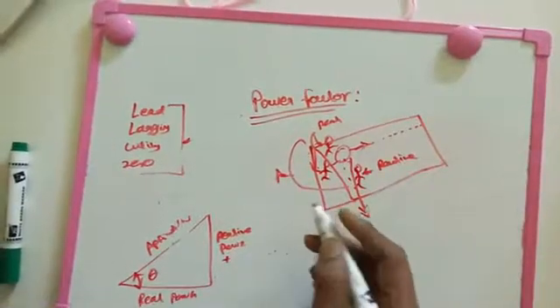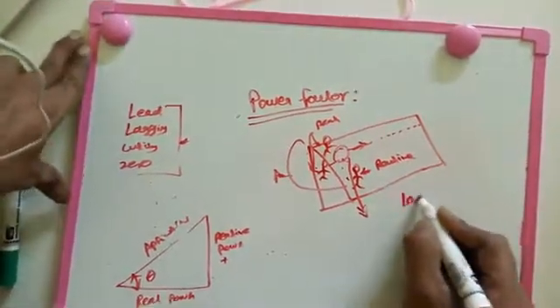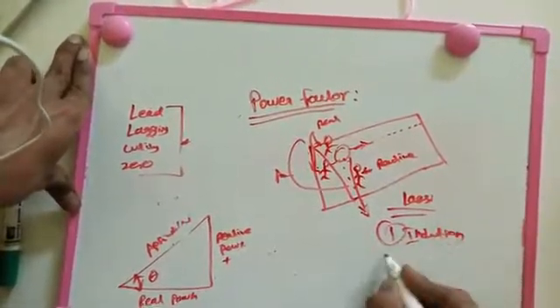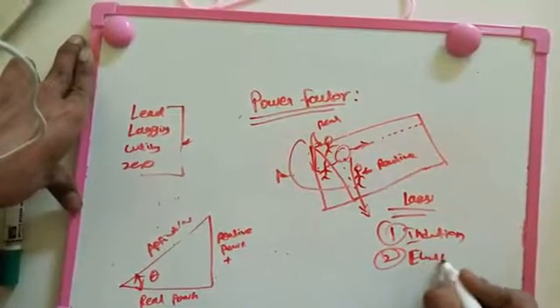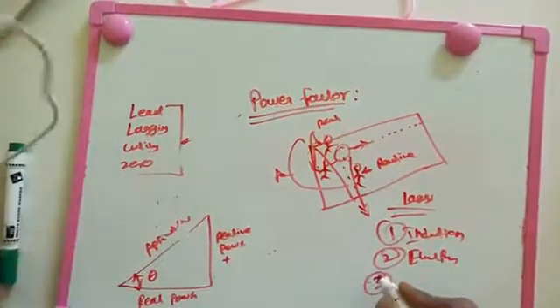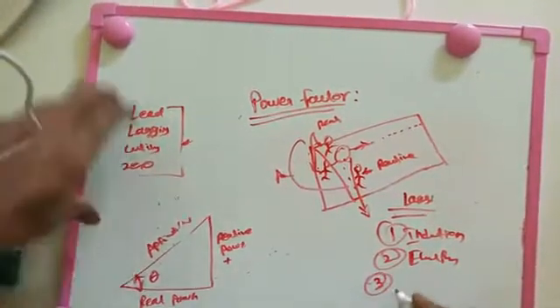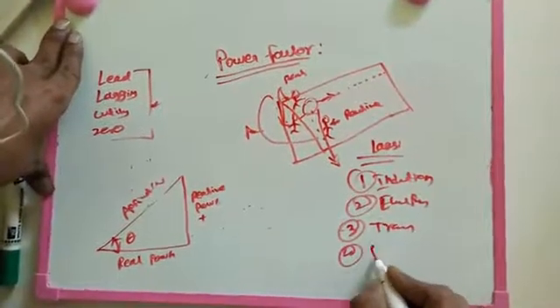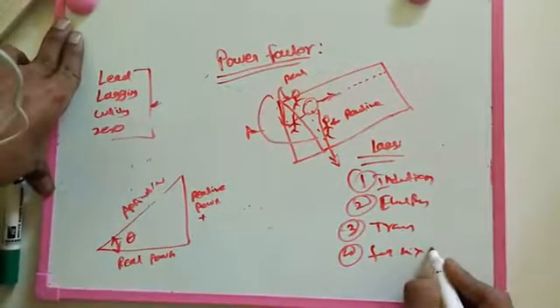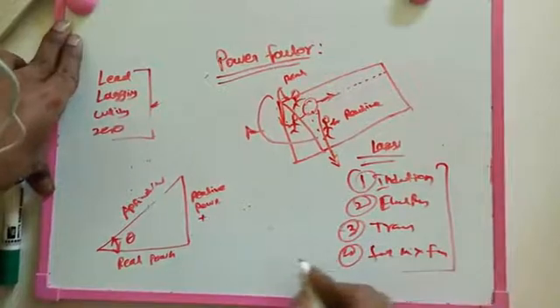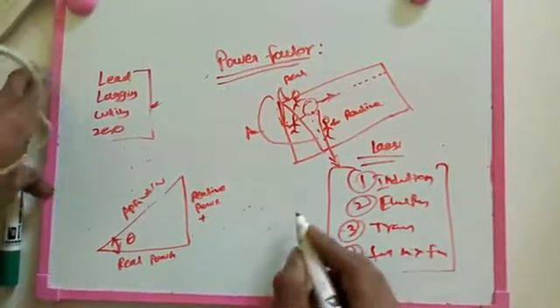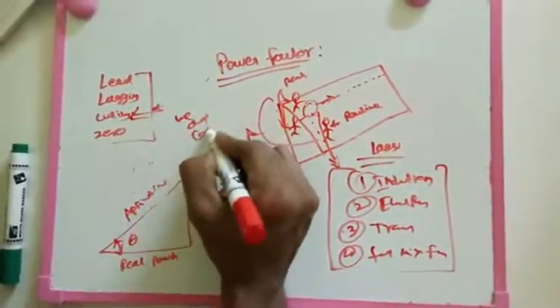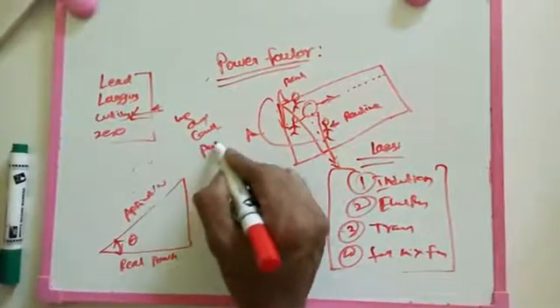Now, what machines have a lagging power factor? First is the induction motor. Second is electrical furnaces. Third is transformers. Fourth is tube lights, mixers, and fans — all these operate with a lagging power factor. To bring the lagging power factor to unity, we add a capacitor bank in parallel to the load.